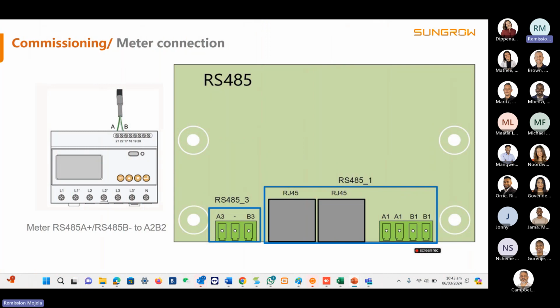And then for the commissioning part, just to remember, as you can see here, one RS485 port is for the Sungrow devices directly, and the other RS485 is for the meter directly. So the meter sits on a different bus from the Sungrow devices. The Sungrow devices will be picked up automatically, but the meter you have to add separately.